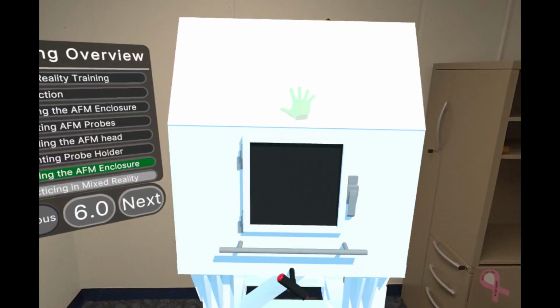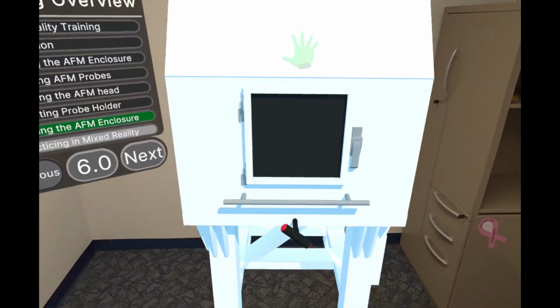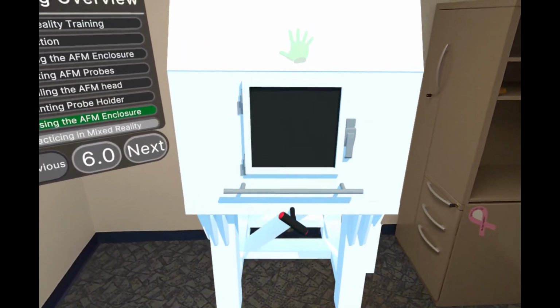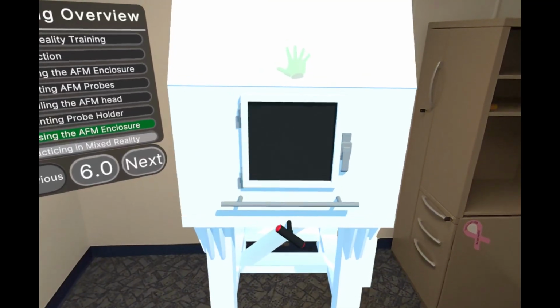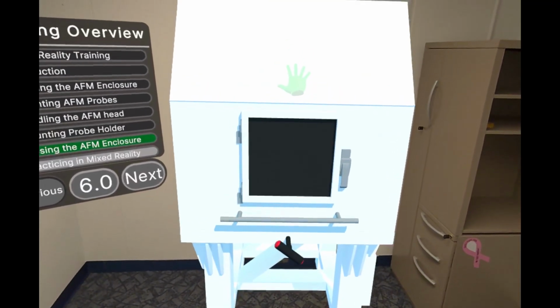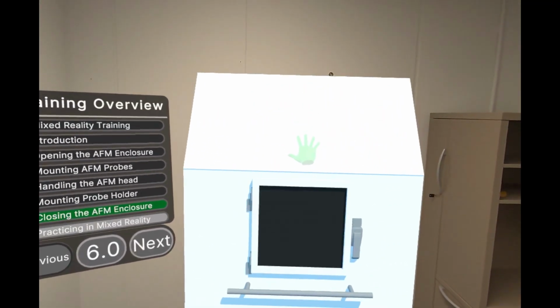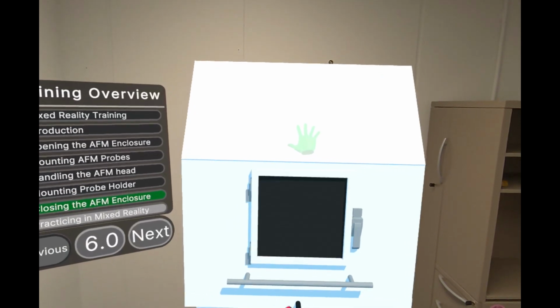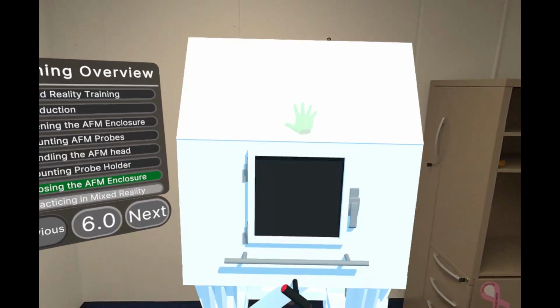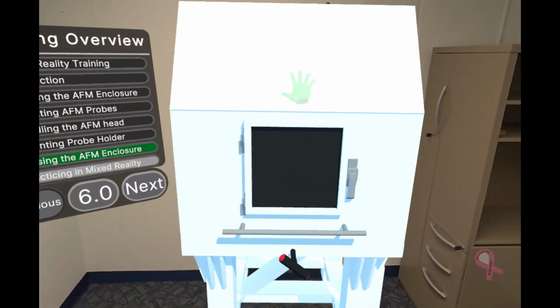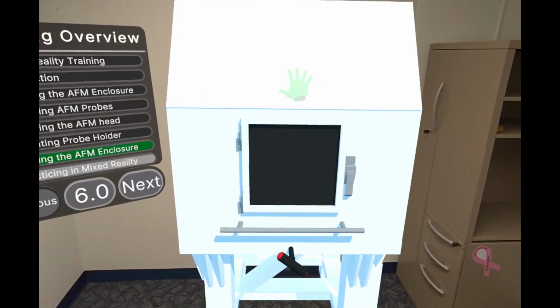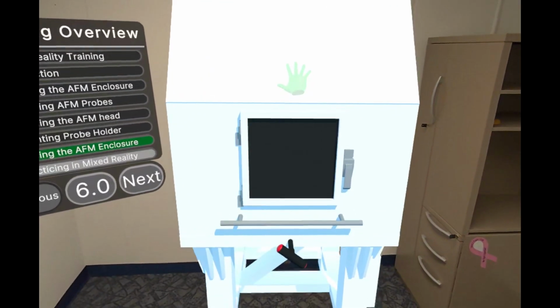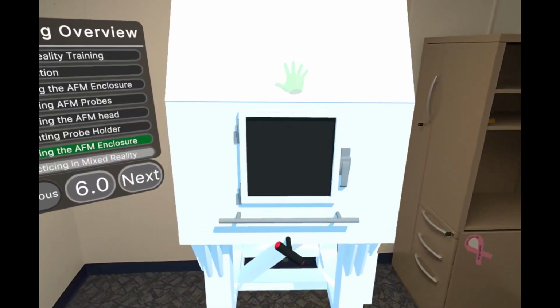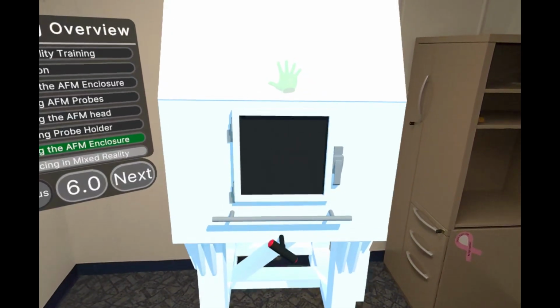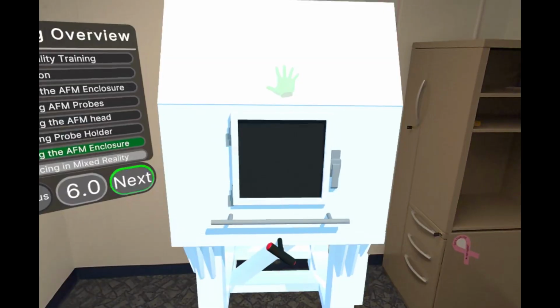Turn the Allen key fully to lock it. It turns about 270 degrees to close and open. If you're having any trouble turning the Allen key, there is likely too much of a gap and you'll need to redo setting the door properly into place. Getting the door closed correctly is important because the system is very sensitive to sound and it needs to be tightly closed to isolate it from all external lab sounds.